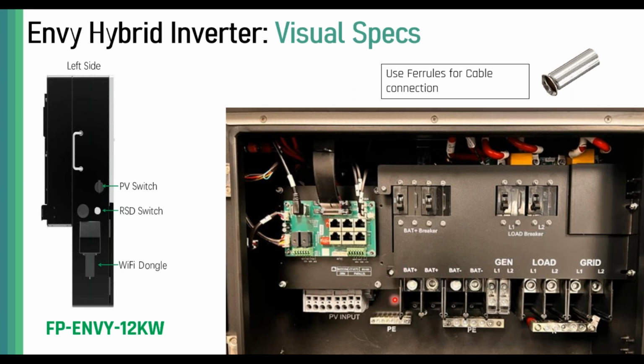And not to mention, as we notice here, these are compression lugs. So we use ferrules, right? We crimp the ferrules onto the bare copper of the battery cable, and then we hook it up directly into the battery port. Battery cable tends to have fine strands, so if you were to hook it up directly into the battery ports, you could actually break some of the fine strands. We might actually consider changing to ring terminals.